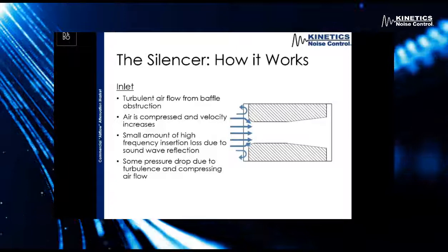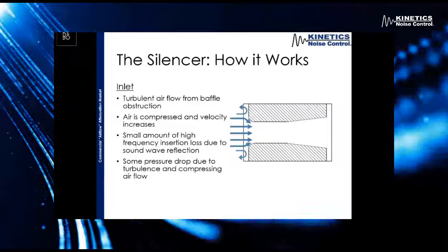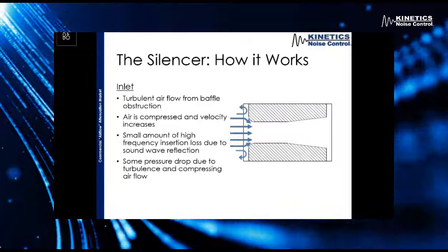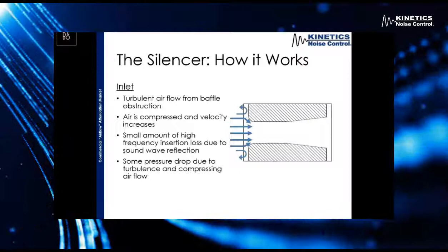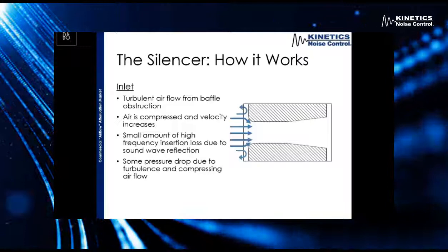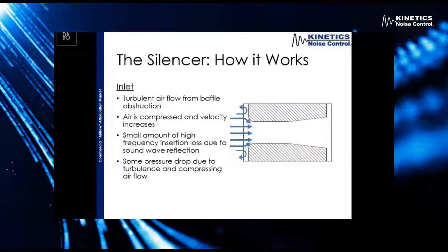There are three stages of how the silencer works, starting with the inlet. This is where we see a lot of turbulent airflow — where the airflow first encounters the silencer. As that air hits the baffle, we get some turbulence. That air is then compressed into the air gap, and the velocity increases as the air is compressed. We'll have a small amount of insertion loss here, specifically in the high frequencies, just due to some sound wave reflection off the baffles. And we get a small amount of pressure drop here due to the turbulence and compression of the airflow.